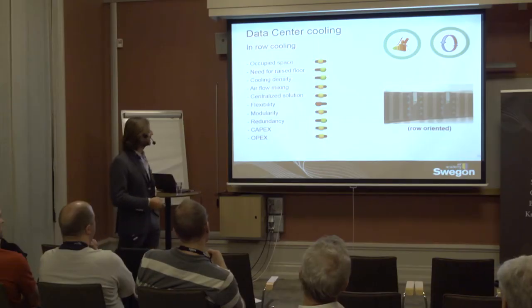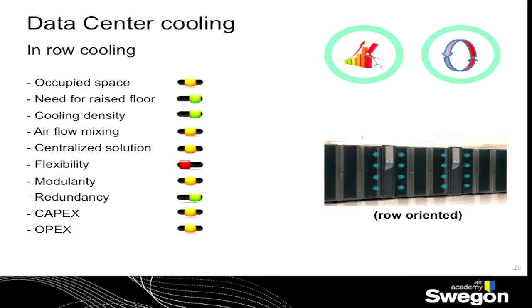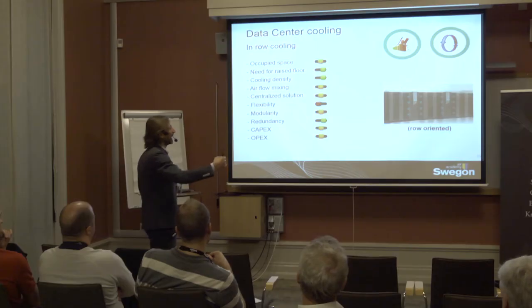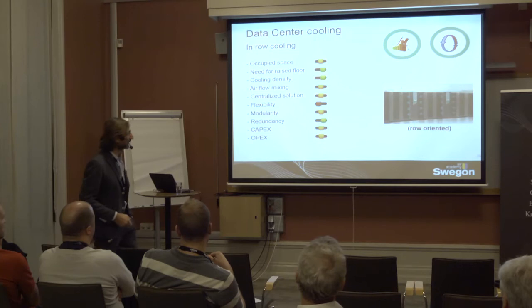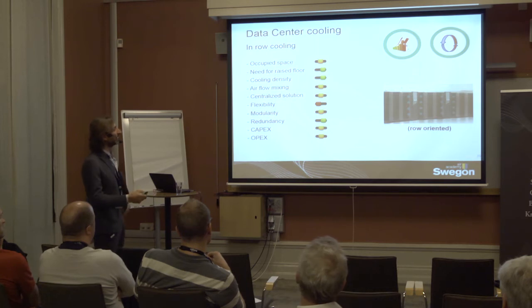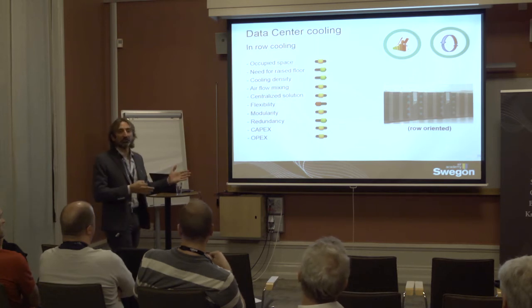To take care of the recirculation and to avoid it, there exists the row-oriented cooling made by the in-row coolers, that increase, of course, the efficiency in terms of airflow mixing. Maybe they are less flexible because you have to put them inside the racks. If you increase the dimension of the data center, you have to provide new machines for every 2 or 3 racks that you put inside the data center. And they take care of the recirculation because, of course, they divide in a natural way the hot side from the cold side.